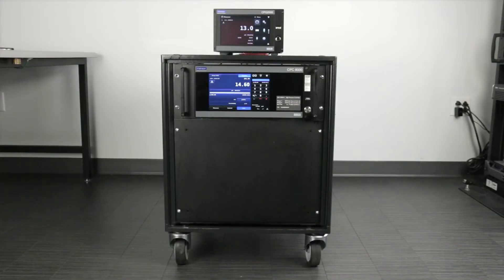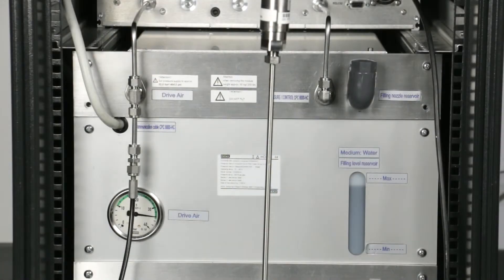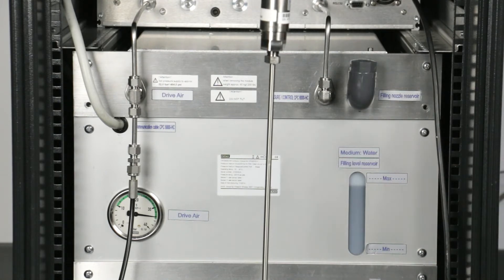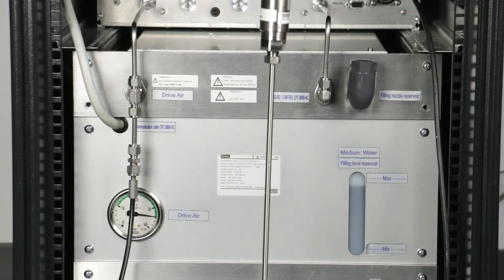The CPC-8000H comes from the factory filled with water, Shell Tellus oil, sebacate oil, or your specified medium. The device under test should be filled with the same hydraulic medium. The fluid level can be checked from the rear panel view window. The media port is used to refill the reservoir when it is below the minimum fill line.